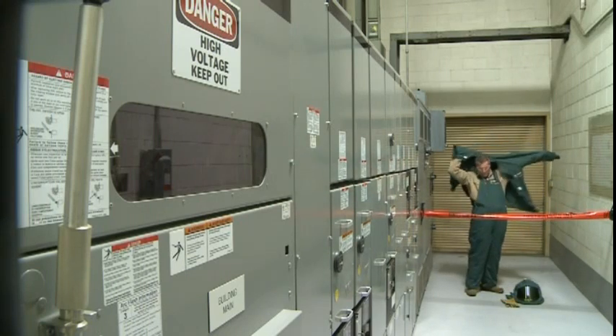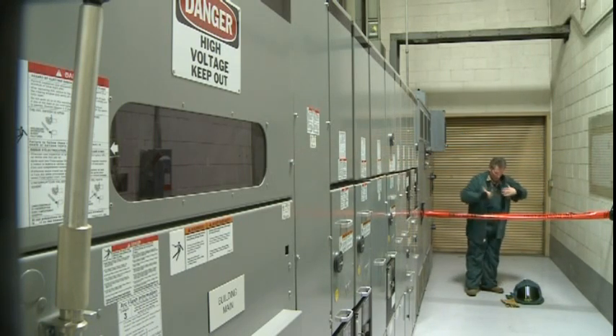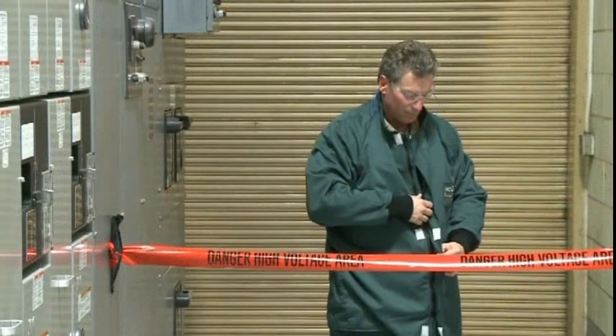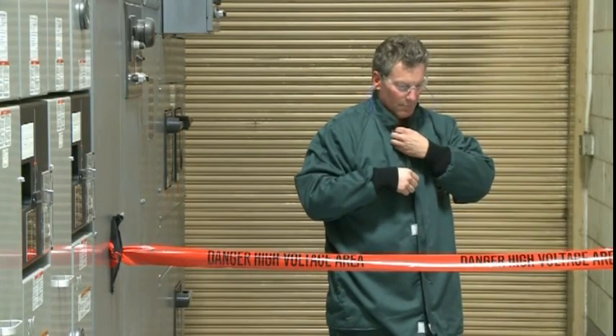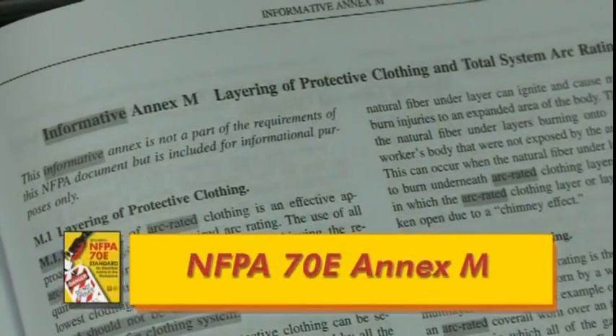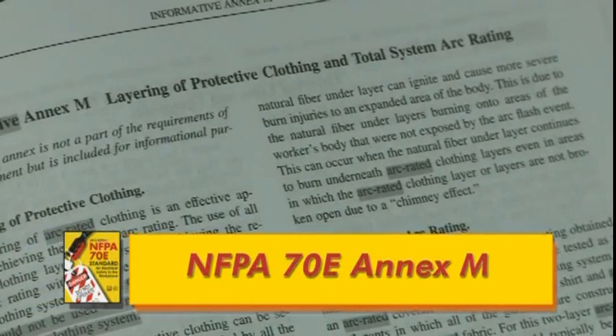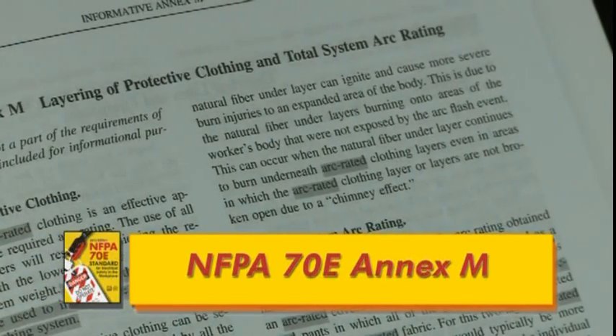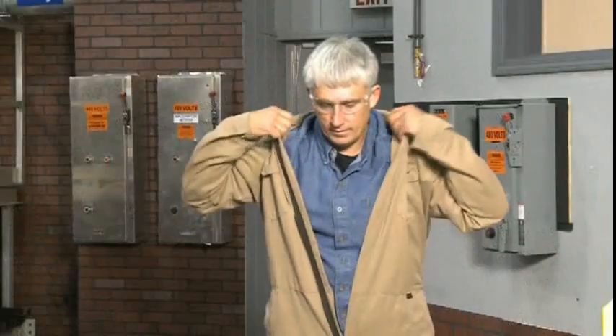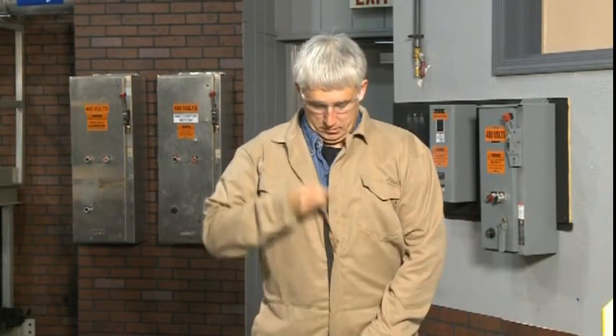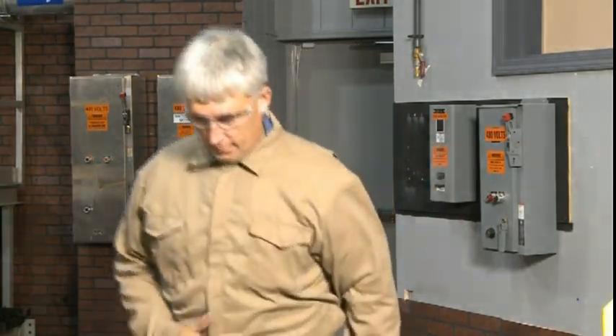Here are some quick tips for dressing for arc flash protection. You may dress in layers of arc-rated material if the rated protection for the layering meets the requirements of the task being performed. Consult NFPA 70E Annex M for the proper way to choose systems with the total calories of protection you need when layering. You need to understand that non-arc rated material, even 100% cotton, cannot be counted towards your total level of protection. Your outermost layer must be made of arc-rated material.